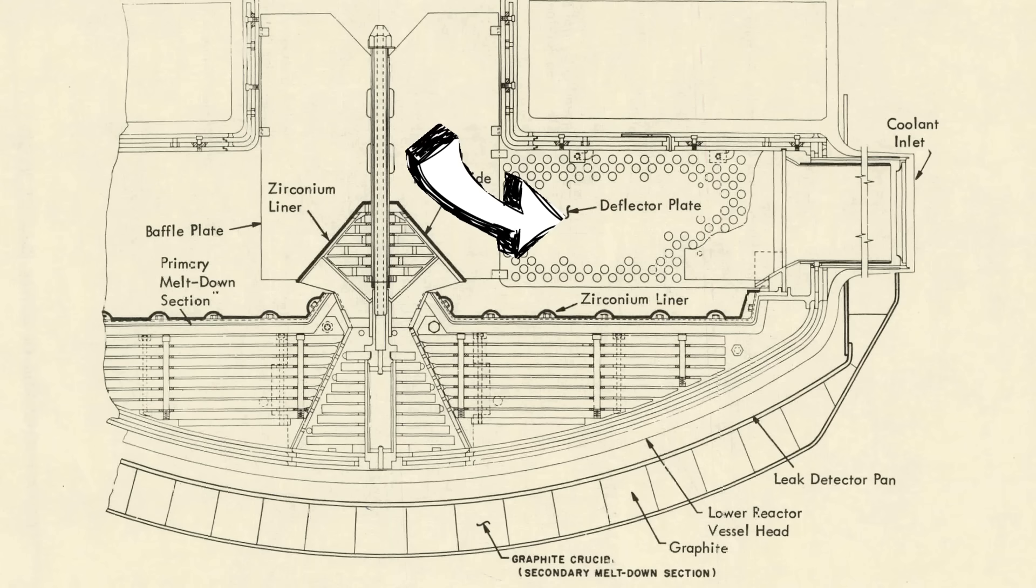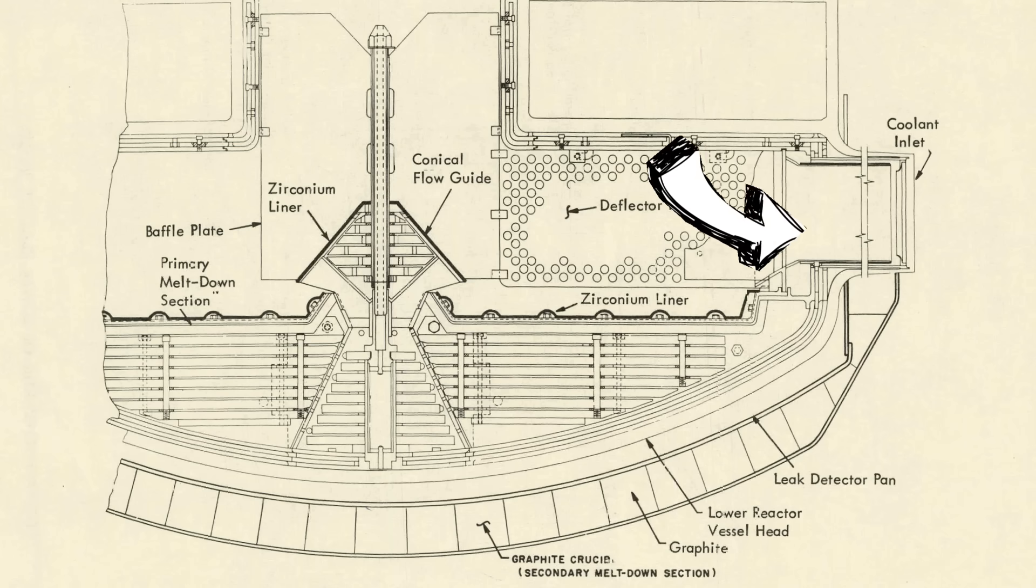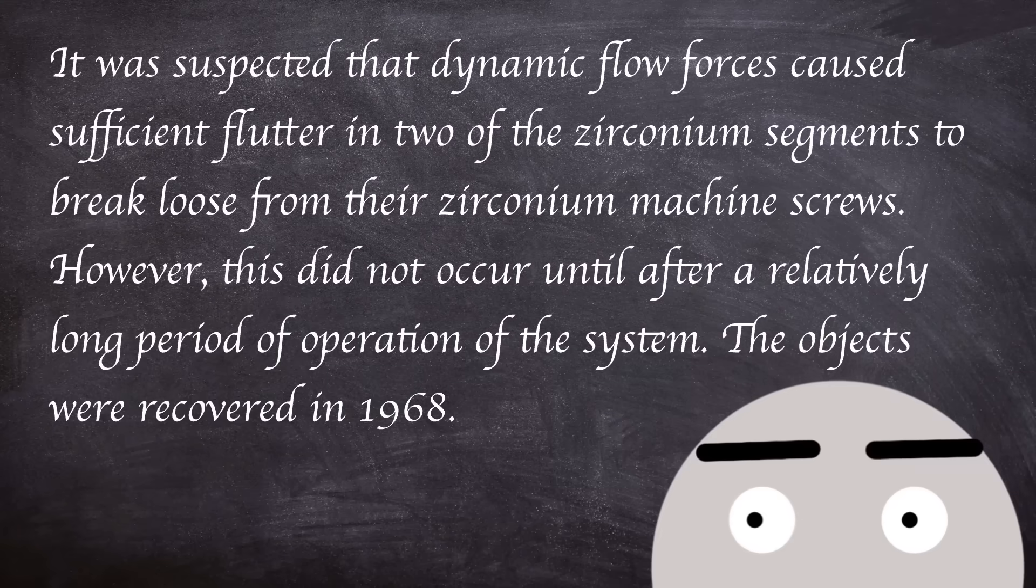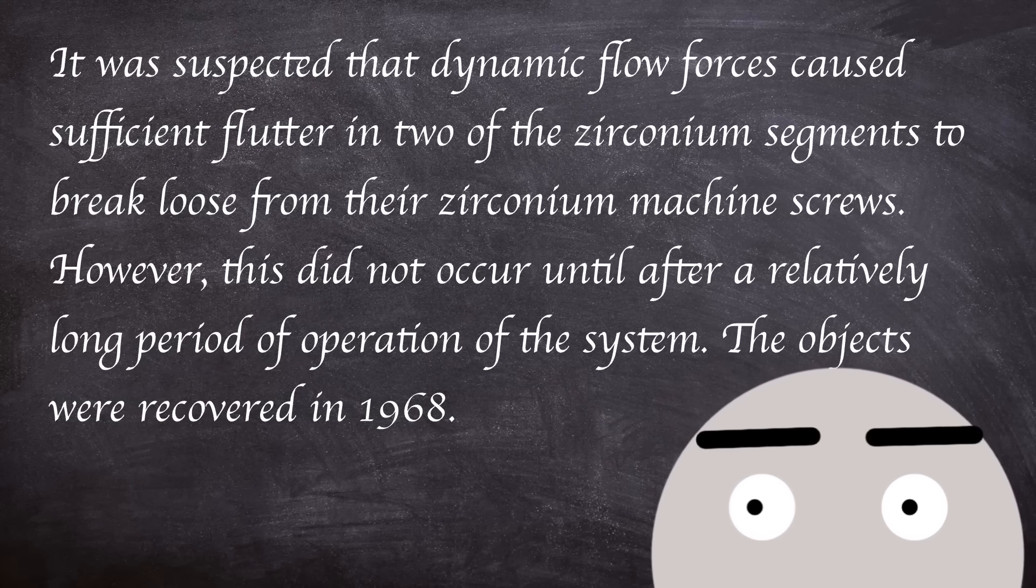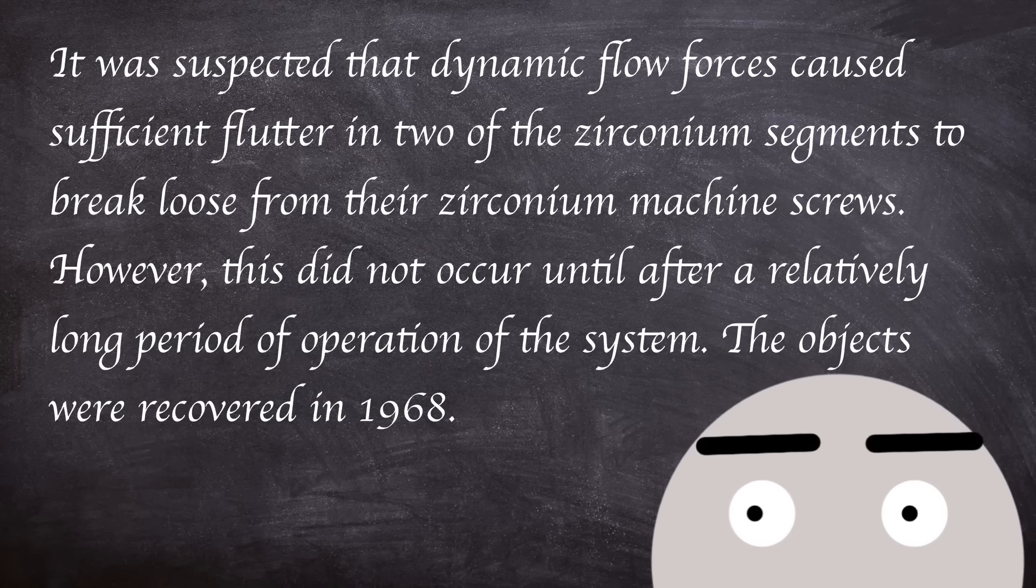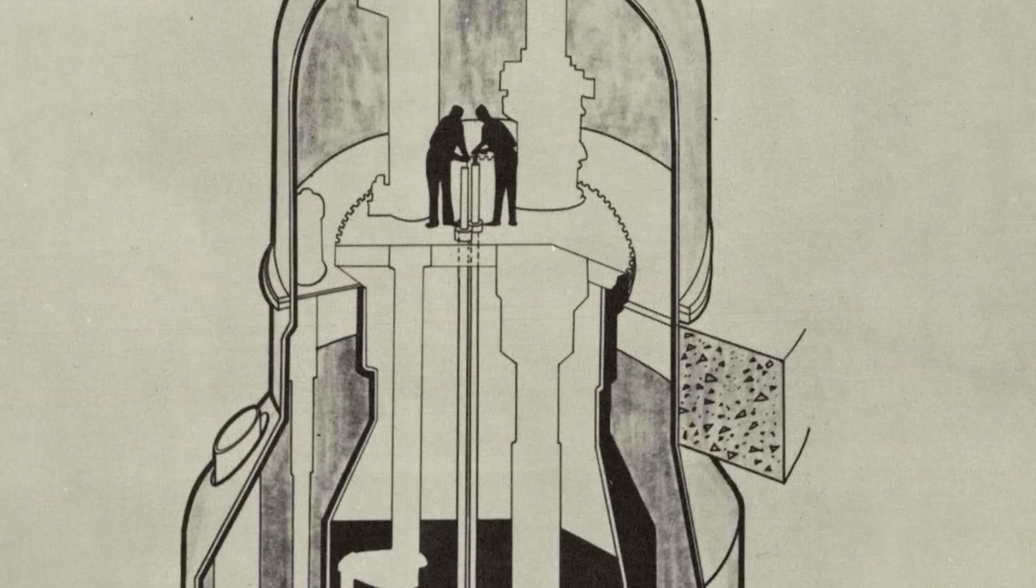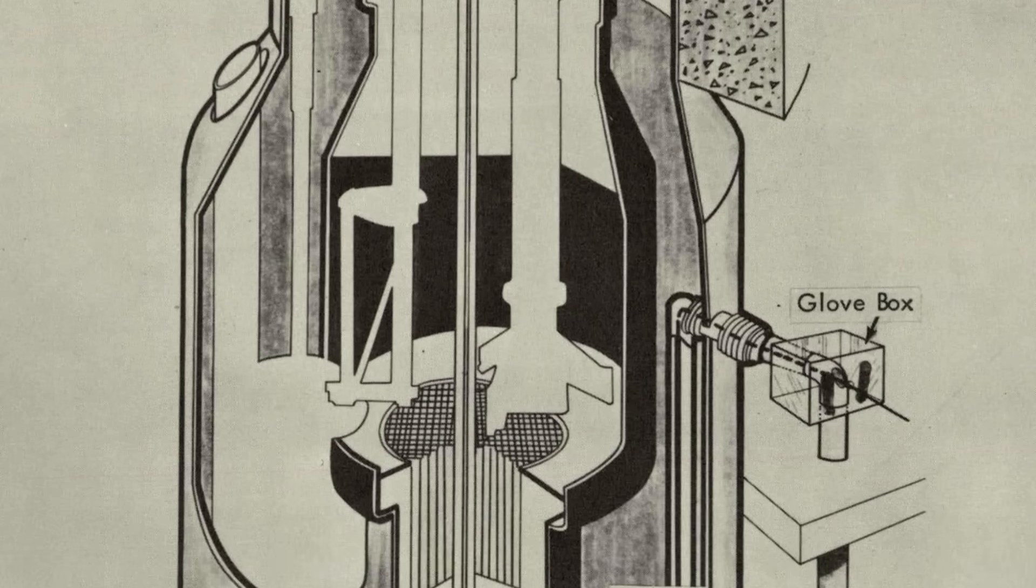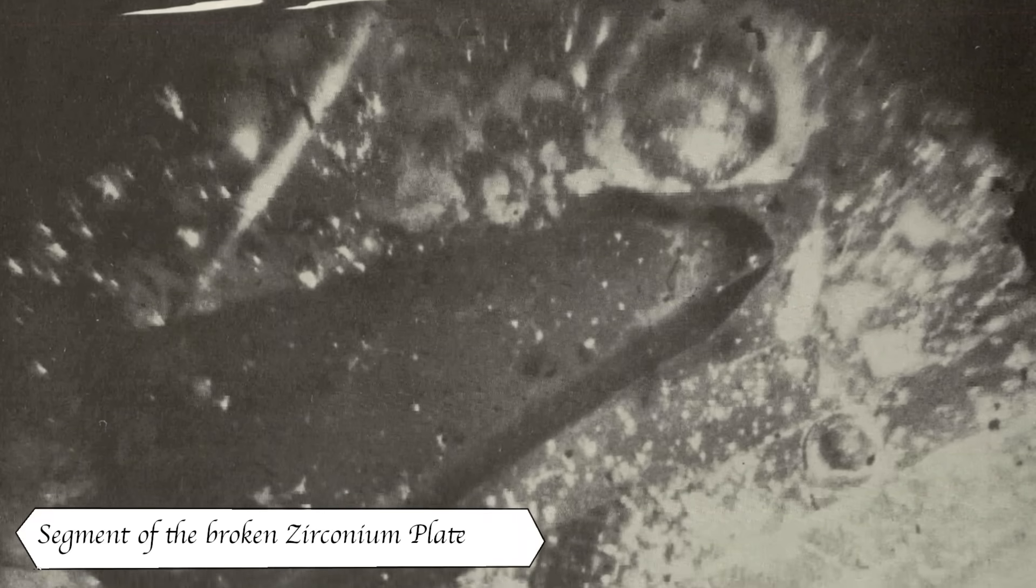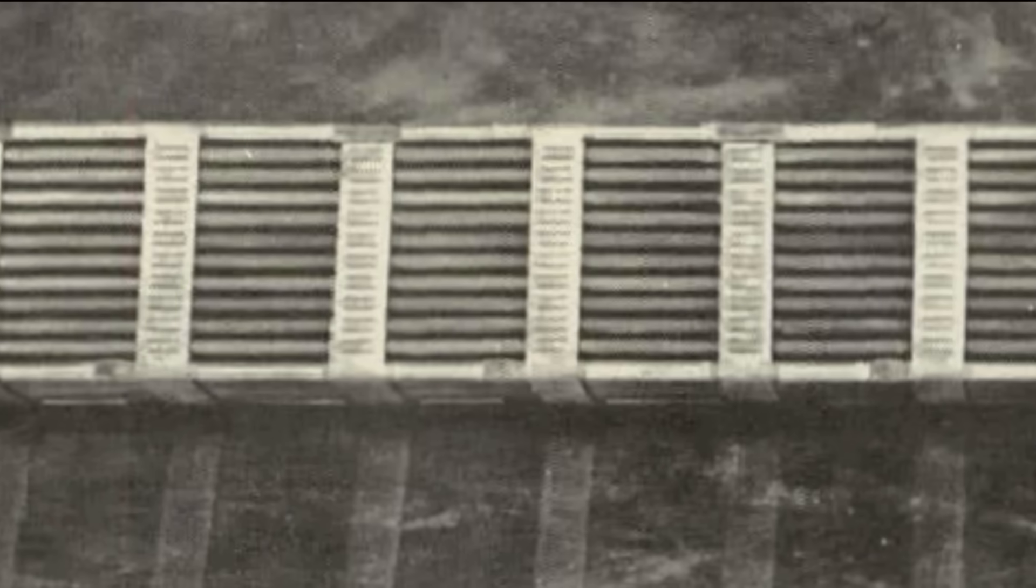The obstruction was part of six zirconium alloy panels used to direct coolant upwards to the reactor. It was suspected that dynamic flow forces caused sufficient flutter in the zirconium segments to break loose from their zirconium machine screws, however this did not occur until a relatively long period of operation of the system. The objects were recovered in March 1968. The repair works to the core used a specially designed remote control tool capable of withstanding the radiation within the reactor. The safety confinement of the primary coolant loop contained an estimated 10,000 curies of radiation. However, this presented a problem in repairing the reactor. Although three elements were damaged, the remainder of the assemblies was still salvageable.